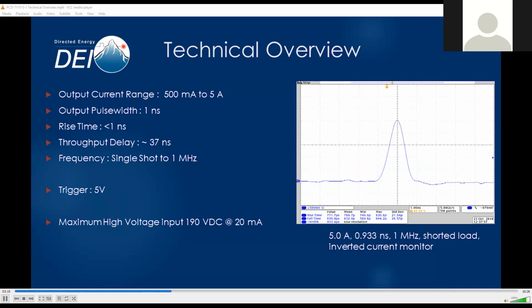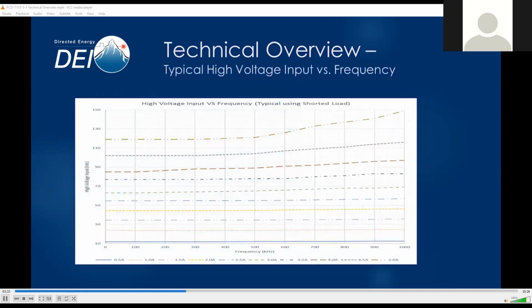The high voltage DC input is 150 volts. In this example, the oscilloscope signal has been inverted to provide a better visual demonstration of the unit's performance. The pulse width is measured at full width half max, or as you can see in this example, at the 2.5 amp level.